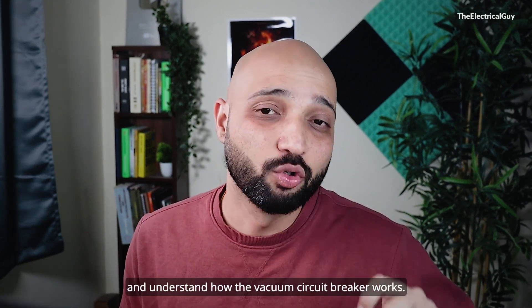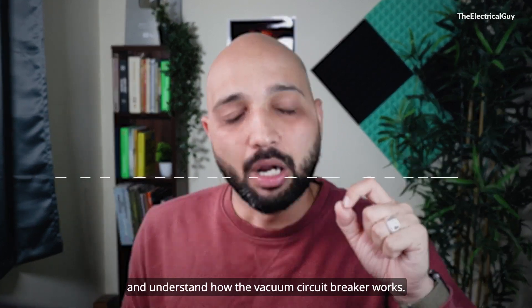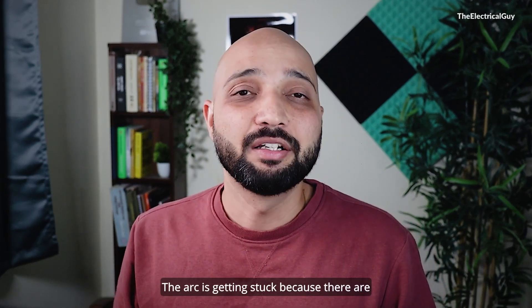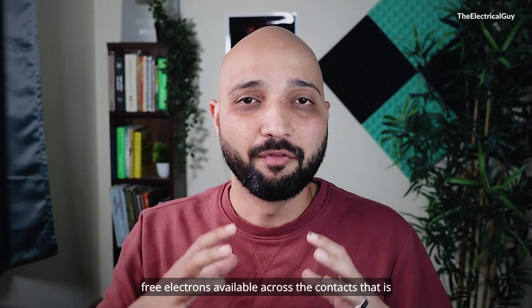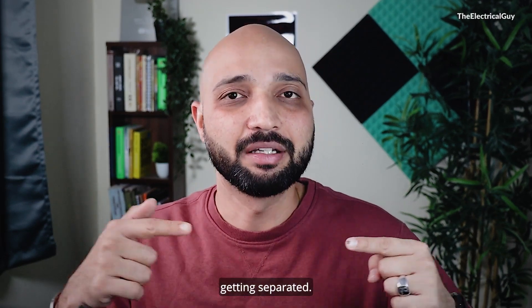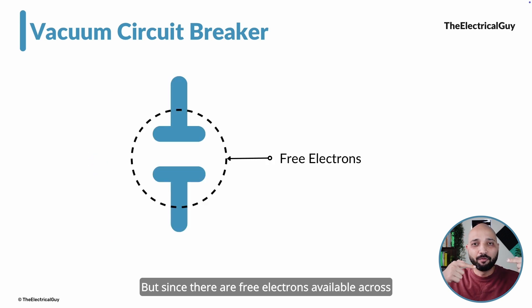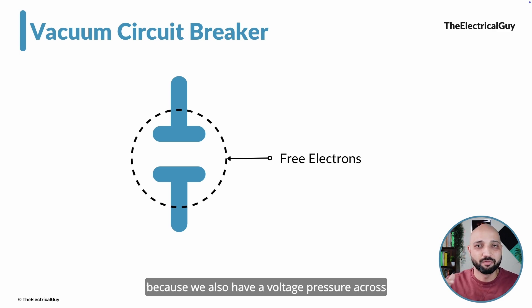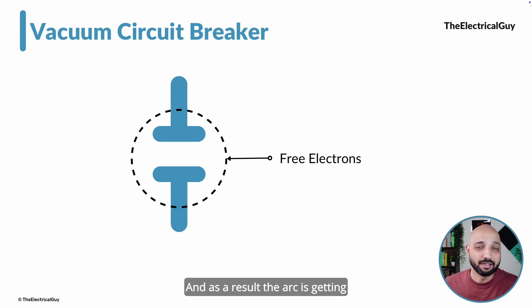Now, if that is clear, let us understand how the vacuum circuit breaker works. To understand that, we need to understand why the arc strikes. The arc is getting stuck because there are free electrons available across the contacts that are being separated. We are opening the contacts to break the current, but since there are free electrons available and we also have a voltage pressure across the contacts, those electrons get ionized and, as a result, the arc is getting stuck.